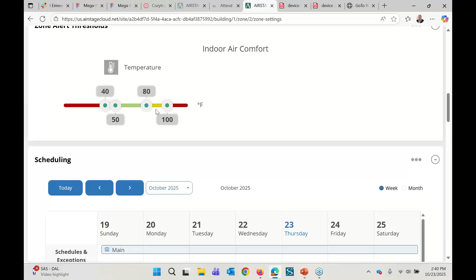Okay. If we scroll down further, you see they have a very simple schedule in here where that system is occupied or unoccupied. So since the system was running at set point, it's knocked itself into standby for the moment, but it's doing exactly what we want it to do. Okay, and how do we know what the schedule looks like? Well, we come down here and we can see that they've got their set point set to 75, the system is on, and that's their unoccupied. And when the system is occupied, they want it to be running at 73 degrees.